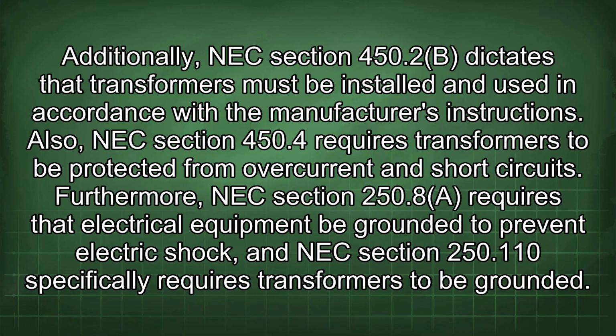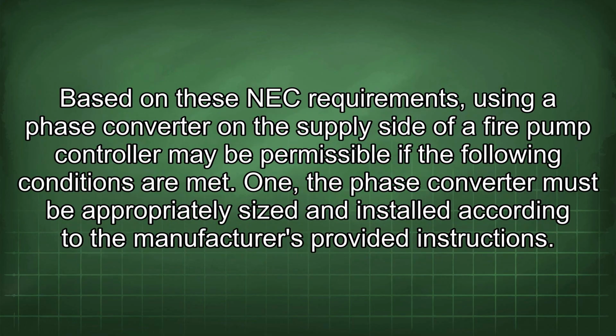Furthermore, NEC Section 250.8 requires that electrical equipment be grounded to prevent electric shock, and NEC Section 250.110 specifically requires transformers to be grounded. Based on these NEC requirements, using a phase converter on the supply side of a fire pump controller may be permissible if the following conditions are met.